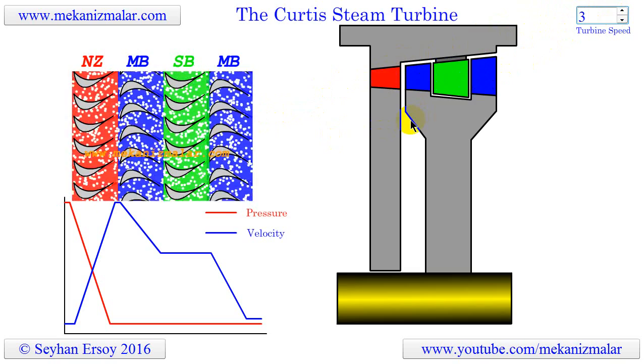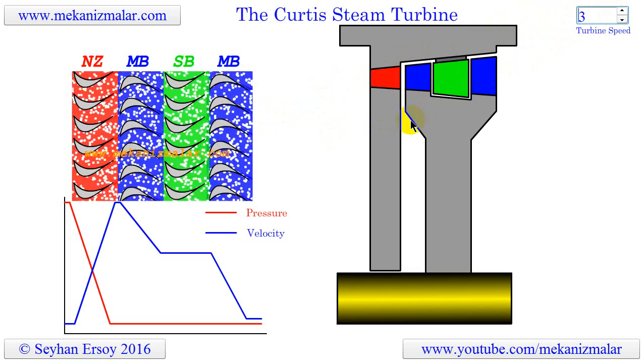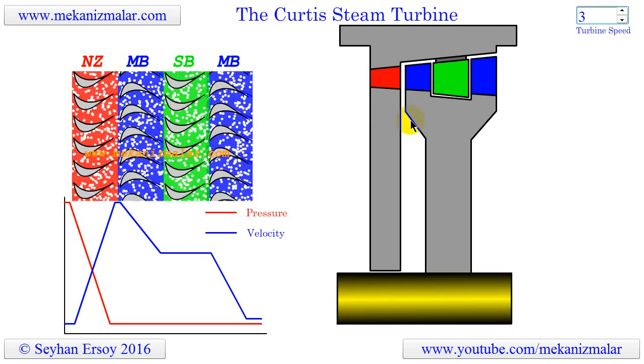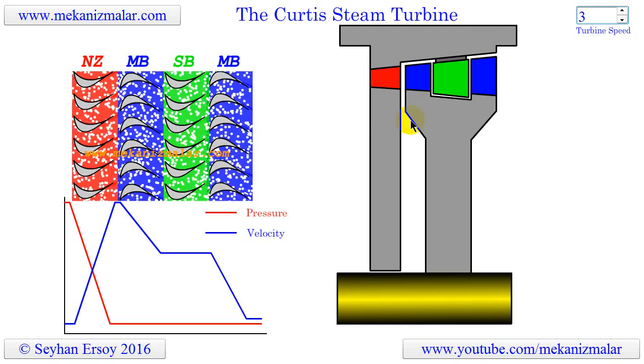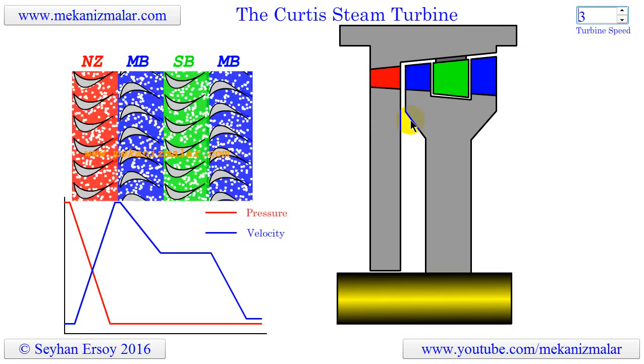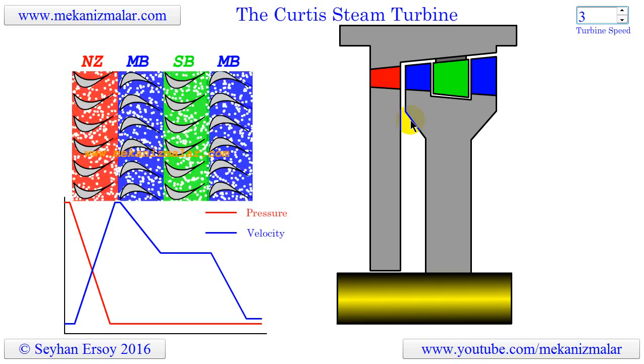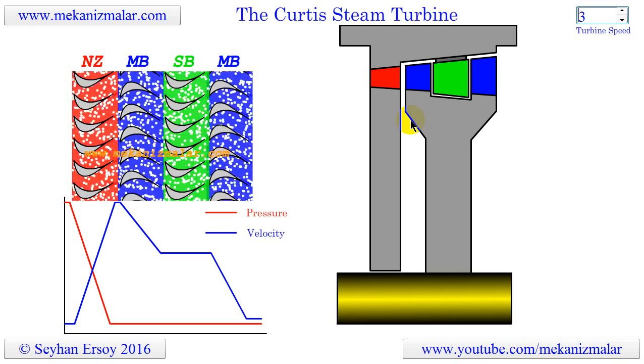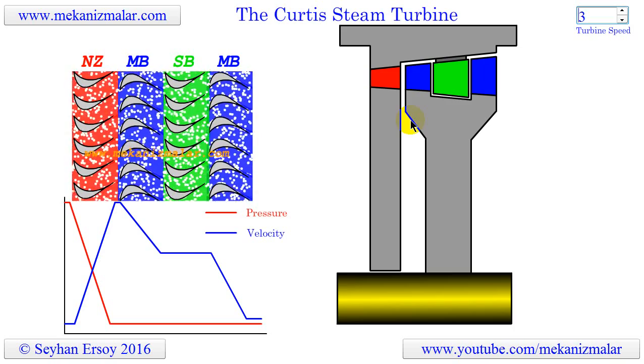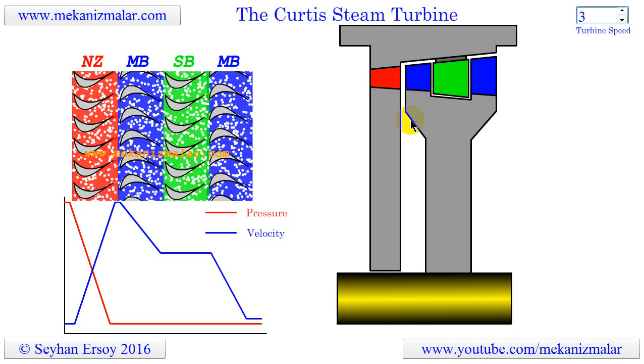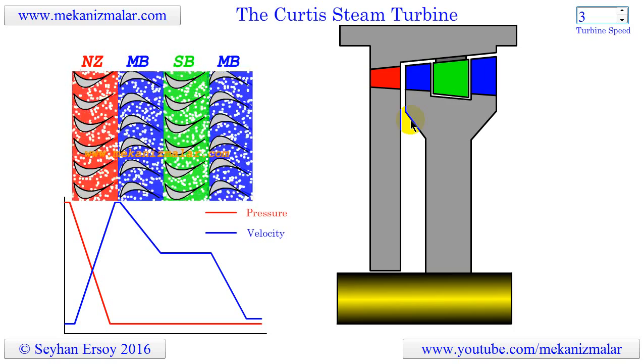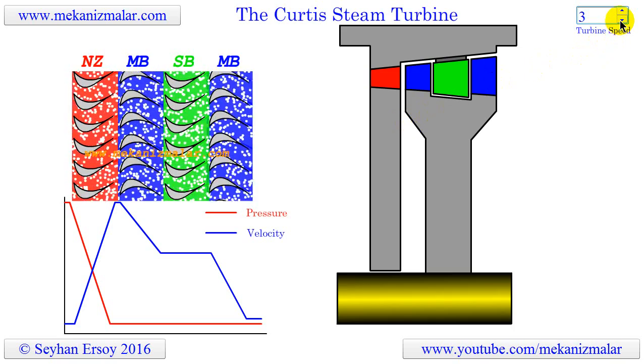In this turbine, rotation of the blades happens in the action direction. In reaction turbines, the steam is ejected from rotating blades, like hot gases ejected from a rocket nozzle. During this process, the rotating blades react to this expelling of the steam by moving in the opposite direction. That is where the name 'reaction' comes from.